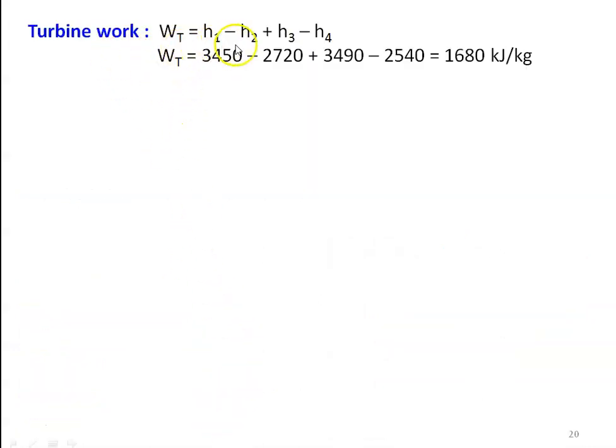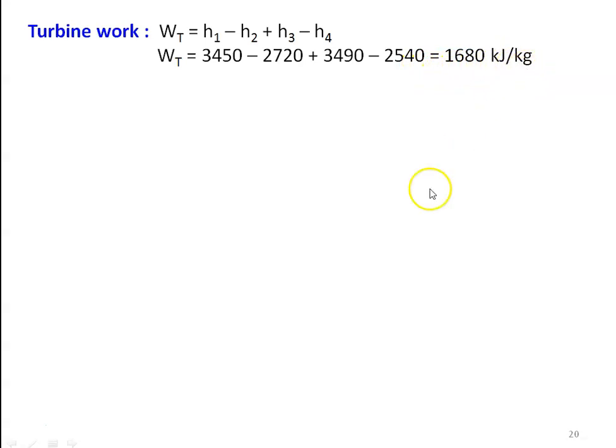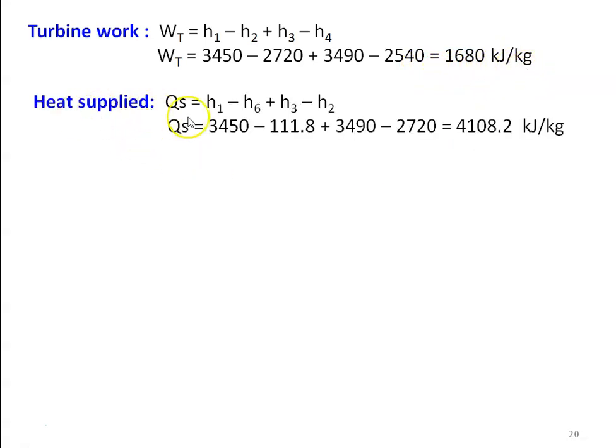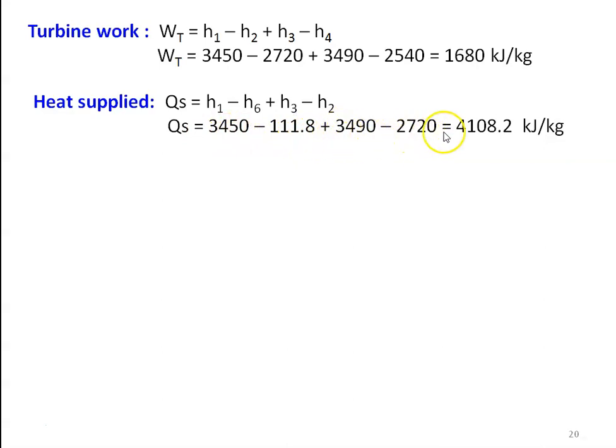Turbine work: Wt = (H1 − H2) + (H3 − H4) = (3450 − 2720) + (3490 − 2540) = 1680 kJ/kg. Heat supplied: Qs = (H1 − H6) + (H3 − H2) = 3450 − 111.8 + (3490 − 2720) = 4108.2 kJ/kg.